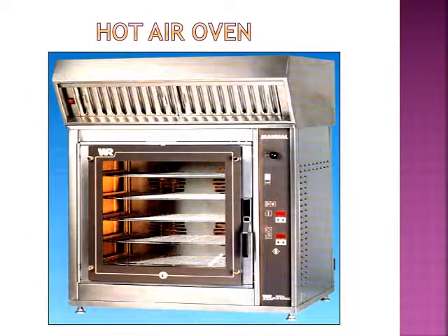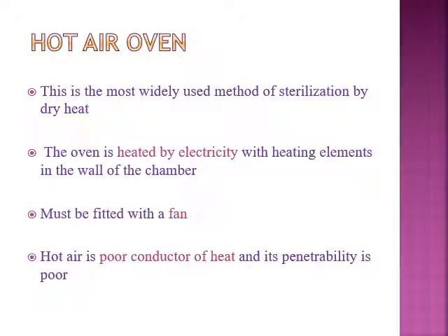So this is the hot air oven. The hot air oven is the most widely used method of sterilization by dry heat. The oven is heated by electricity with heating elements in the wall of the chamber. It must be fitted with a fan. Hot air is a poor conductor of heat and its penetrability is poor.